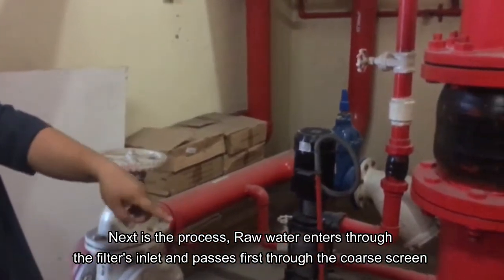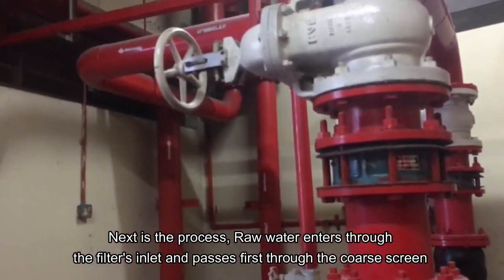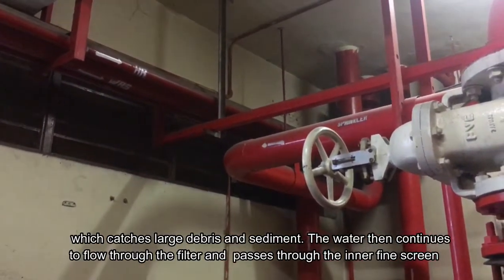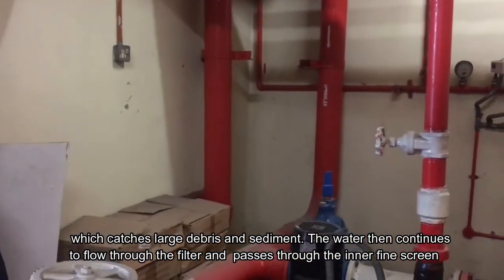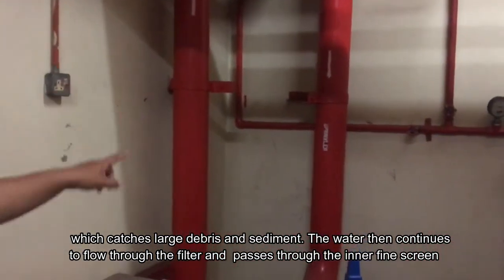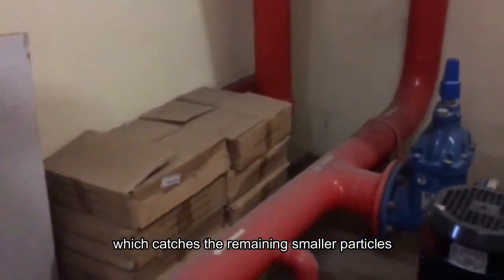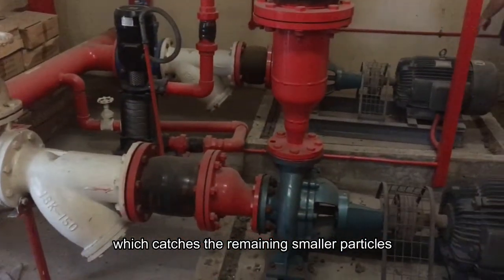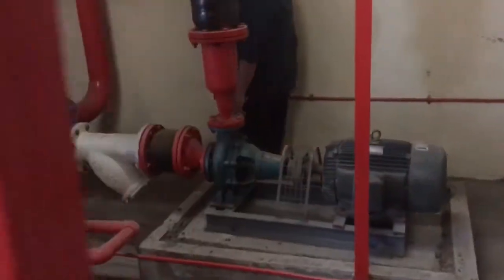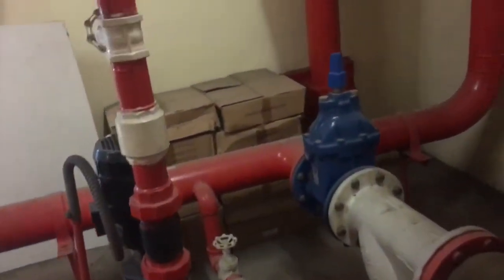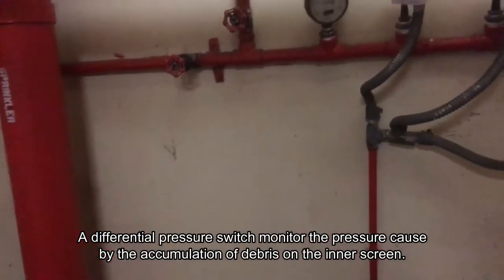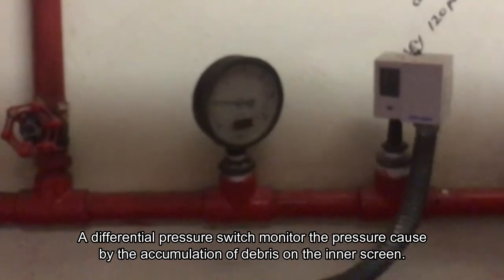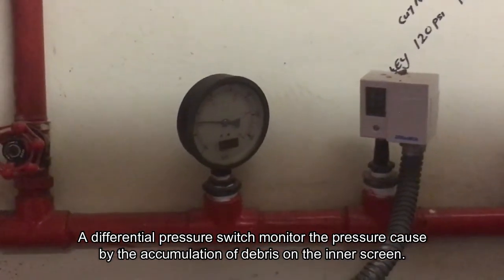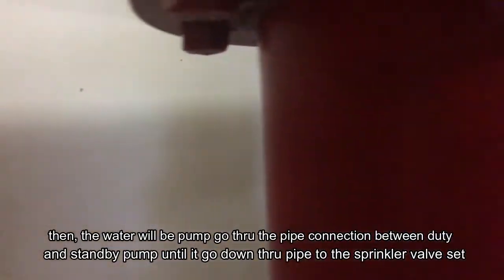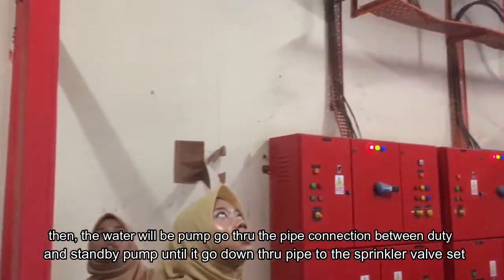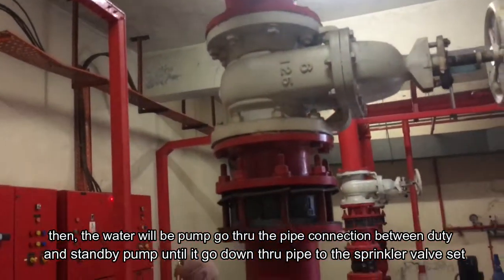Next is the process. Raw water enters through the filter's inlet and passes first through the coarse screen, which catches large debris and sediment. The water then continues to flow through the filter and passes through the inner fine screen, which catches the remaining smaller particles. A differential pressure switch monitors the pressure caused by the accumulation of debris on the inner screen. Then the water will be pumped through the pipe connection between the duty and standby pump until it goes down through the pipe to the sprinkler valve set.